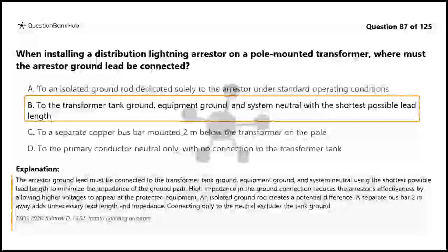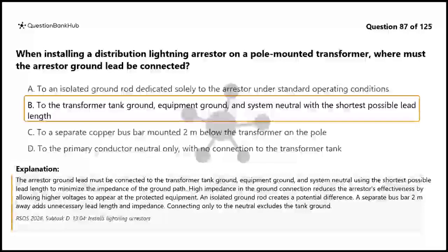The arrestor ground lead must be connected to the transformer tank ground, equipment ground, and system neutral using the shortest possible lead length to minimize the impedance of the ground path. High impedance in the ground connection reduces the arrestor's effectiveness by allowing higher voltages to appear at the protected equipment. An isolated ground rod creates a potential difference. A separate bus bar 2 meters away adds unnecessary lead length and impedance. Connecting only to the neutral excludes the tank ground.